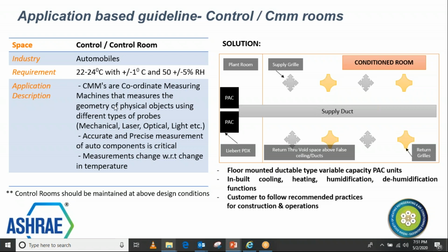And you can see that some applications may demand a floor mount ductable kind of precision AC, which can be installed in a plant room, and you can take the supply from the duct. Or these units can also be installed on a floor stand and discharge the cold air from the front, if it's a smaller control room where the units can be installed in the same room, and it's easy to have a return and supply pattern. So this will depend on site to site. Most sites in control rooms will obviously use the ductable system because of the industrial complexity in terms of the layout and the overall building structure and many other things. And obviously the false floor, access floor, is not available in most of these applications.